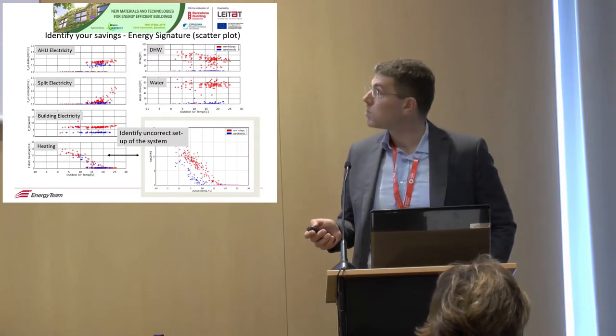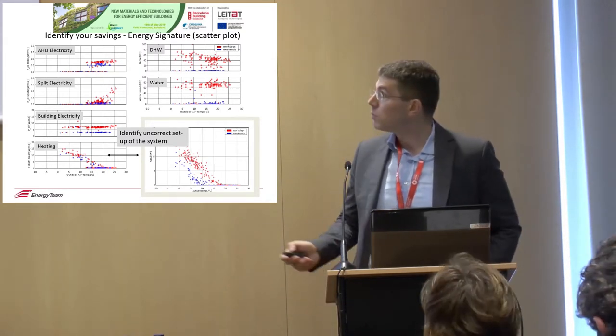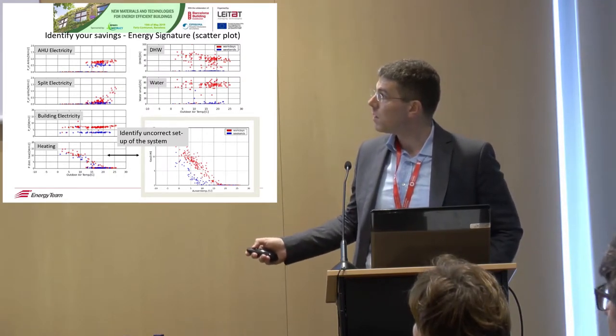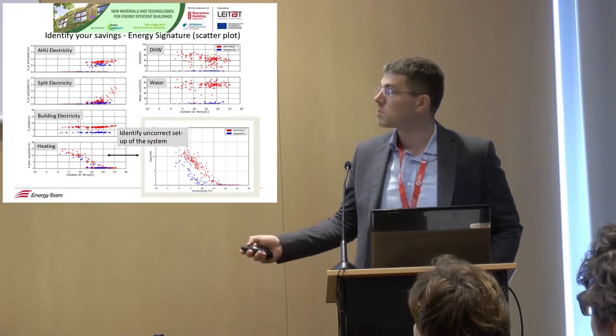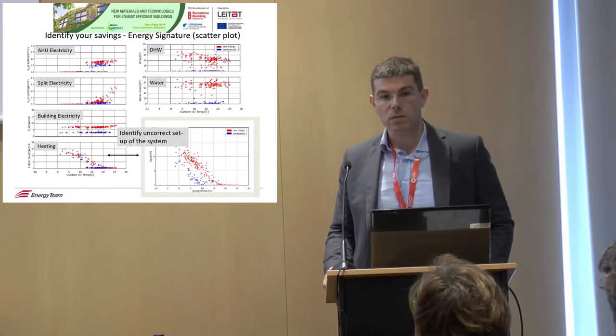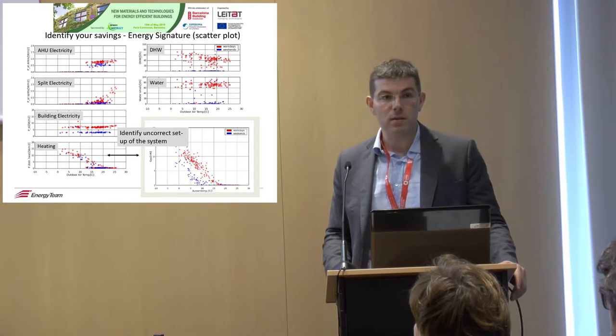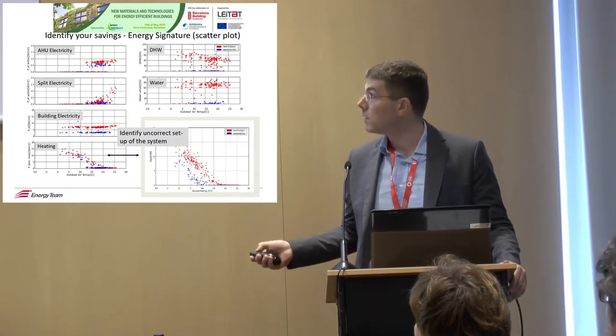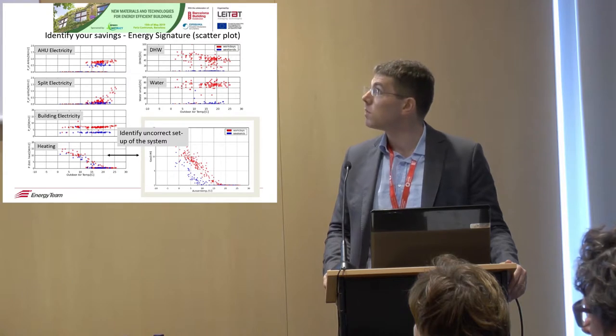Here you can see how identifying different energy signatures of the building helps you identify incorrect set point setups in the system. This is the previous energy signature compared to one that is not as expected. In a simpler way, with an increasing amount of data, once you define the rule that explains the energy behavior of the building, you can more easily highlight and correct system setups that may occur during the building's usage.